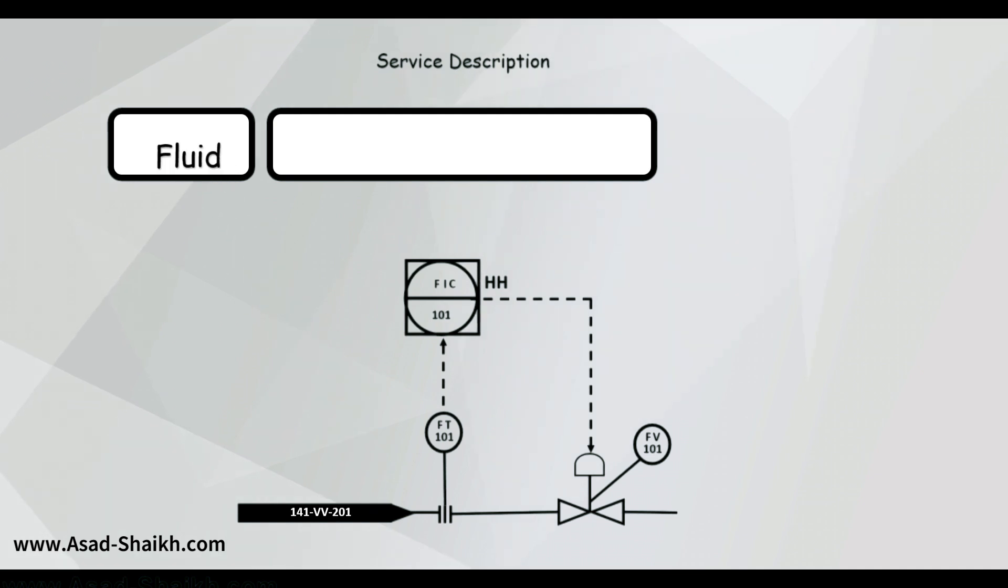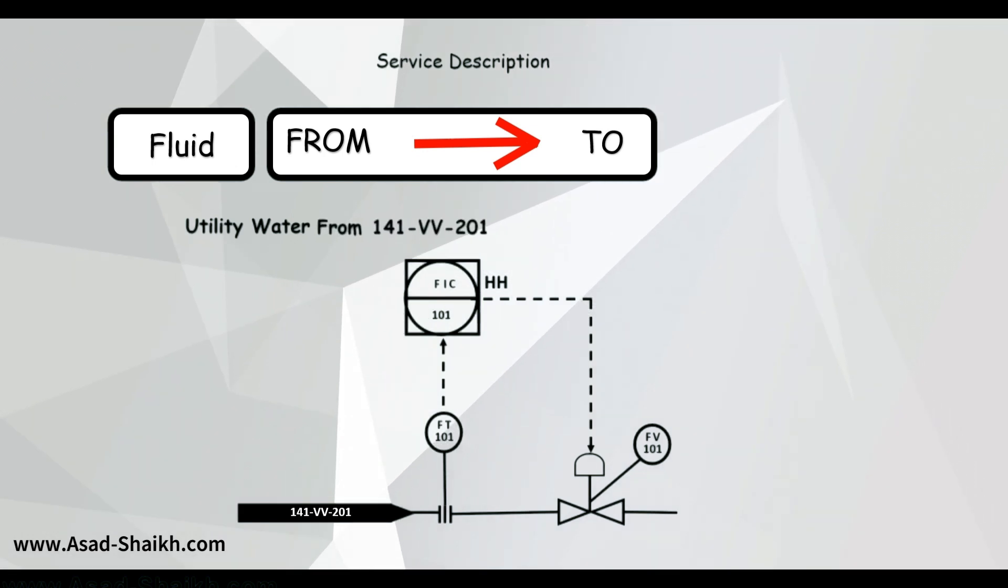Let us talk about the most common ways to enter service description. It is broken down into three important components. The first one being what is the fluid. Let us take an example. So if you see here for our case let us imagine that utility water is flowing through it. So next important thing is from where is it coming. And then you have where is it going to. So the from-to concept comes into picture. So if you see here for example it comes from an equipment VV201 and then it goes to a pump suction which is 141 PC 301. So an operator when he is looking at the DCS would know okay fine utility water is going from this section to this section.